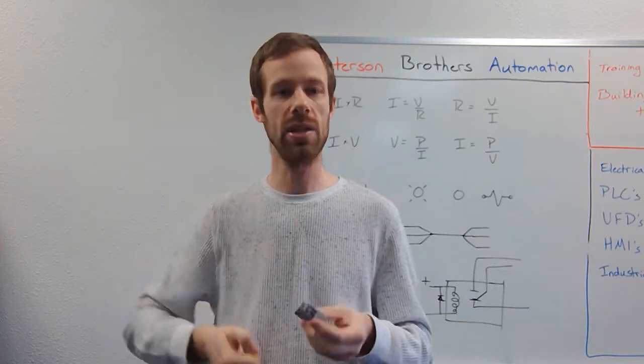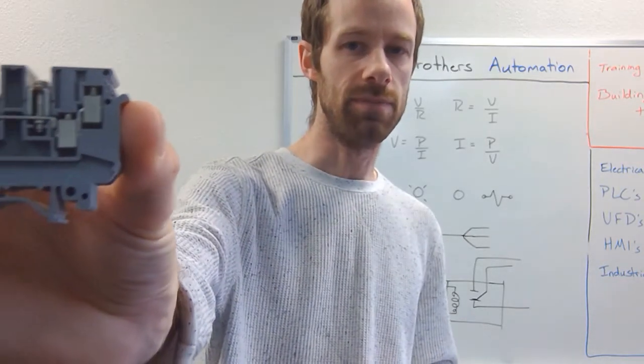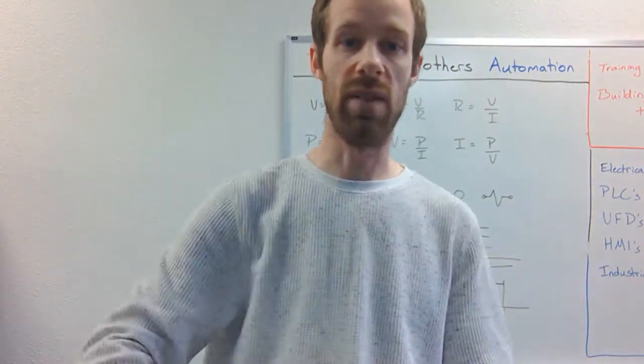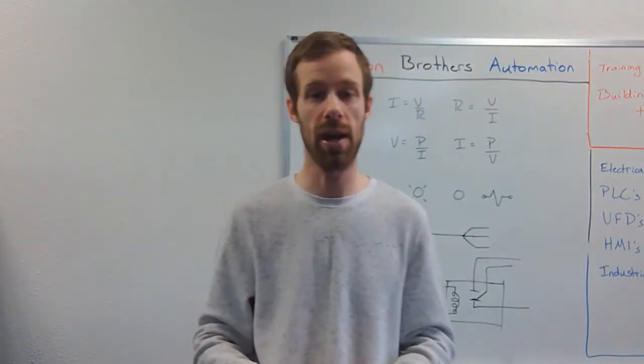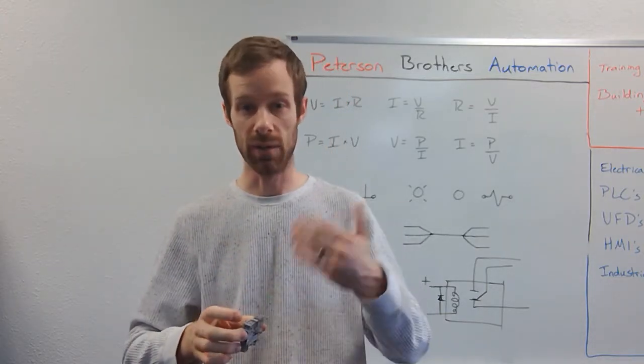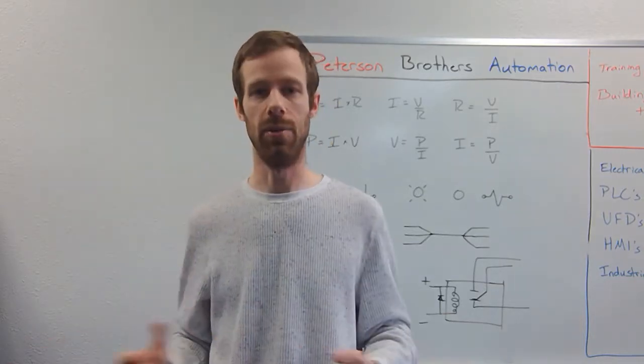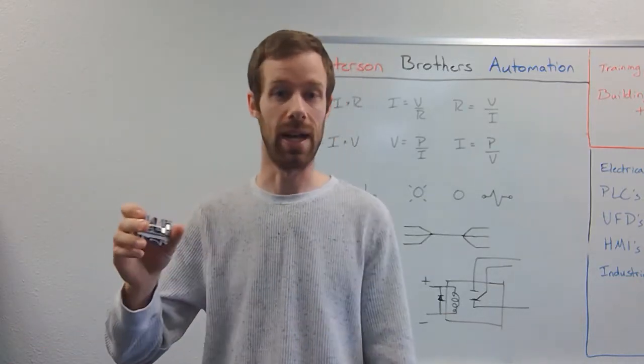If you torque it down way too much, the screws holding this thing down, they're not that beefy. So we can't just take a big screwdriver and just tighten it down because it'll strip all the threads out. We also don't want to tighten it down too little because then it might vibrate and fall back out, and then our jumper is lost. And then why do half of our load devices not work? Oh, it's just because one jumper fell out.